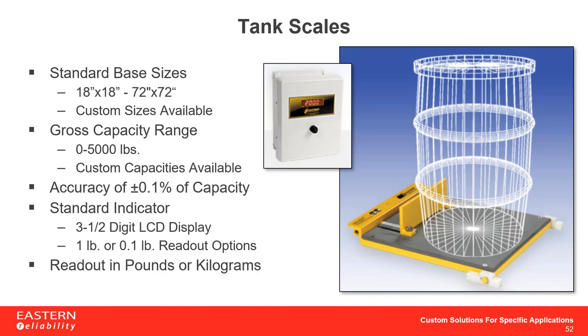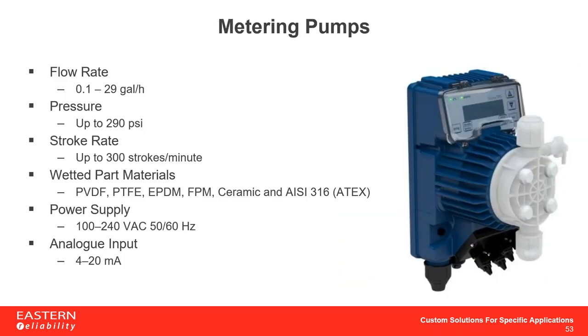We also have metering pumps. The two key components I typically need in order to get you the right metering pump are the flow rate you're looking to achieve and the pressure — they go hand in hand. The wetted parts on these metering pumps are compatible with most of the chemicals typically seen in chemical feed stations, and they accept a 4-20 milliamp signal.